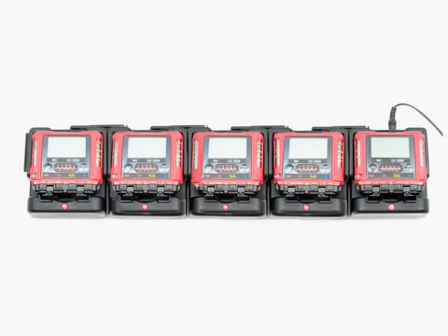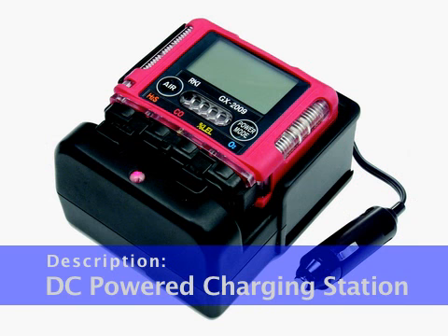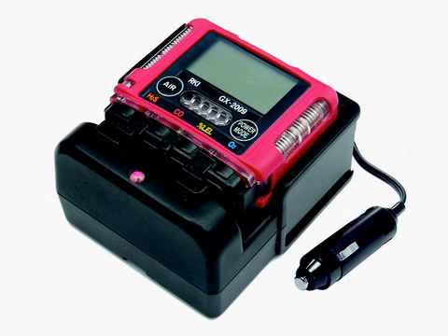Charging stations for more than one instrument include additional chargers that are attached to each other. The same AC adapter can power up to a maximum of 5 charging bases. An optional DC-powered single-instrument charging station is available with a 12-volt DC vehicle plug. The DC adapter for the charging station can only provide enough power to charge one instrument at a time, so the DC-powered charging station is only available as a single-instrument charging station. It uses the same charging base as the AC-powered charging station.